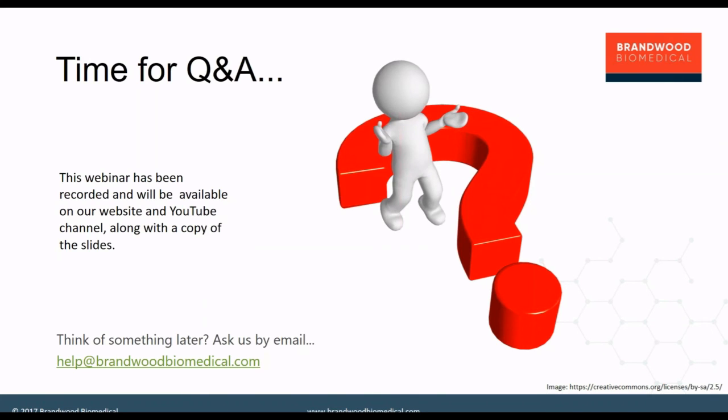If you do follow the latest version of that standard, you're following the latest test method, essentially, to demonstrate compliance with the regulation. The other aspect is, once you can demonstrate through the technical file that the latest versions of the standards have been applied, another thing that the regulator may look into is whether your clinical evidence is actually up to date, and the body of knowledge captured within your technical evidence reflects current clinical practices.